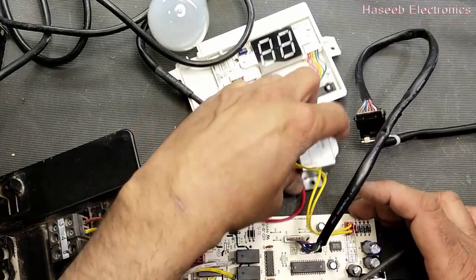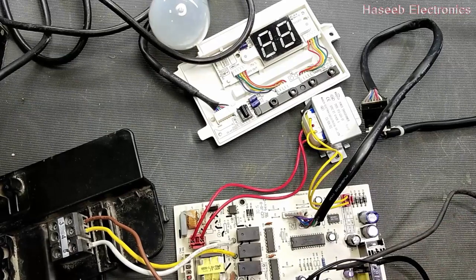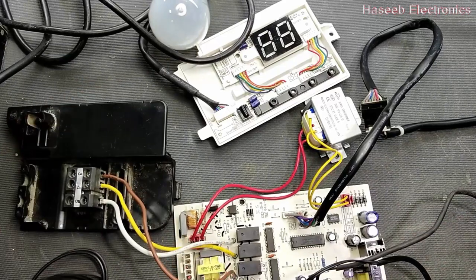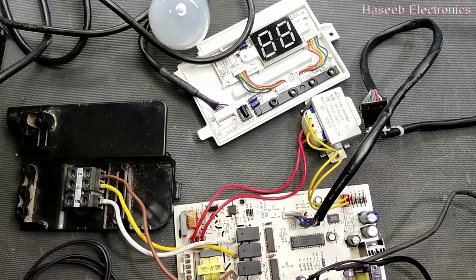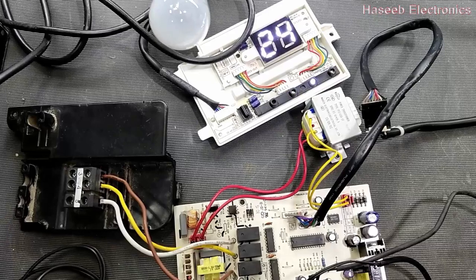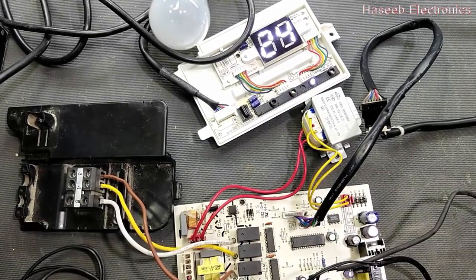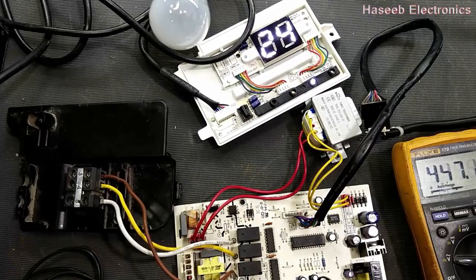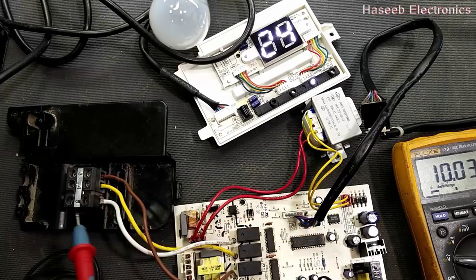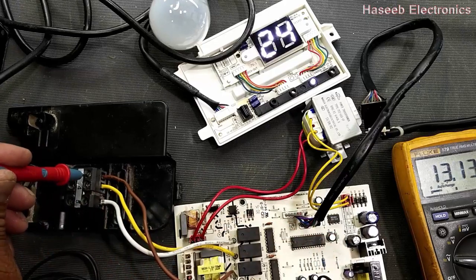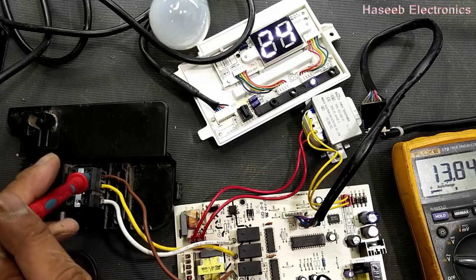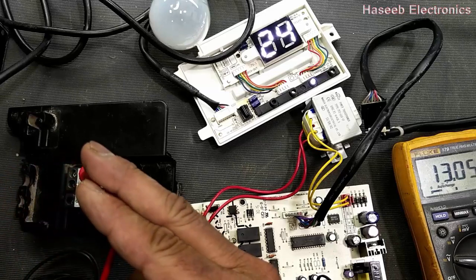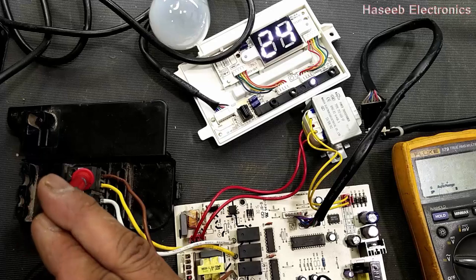Now I will share the most common failures of this board. First I have to turn it on. Now it is powered on. Set the multimeter to AC voltage. Put one lead at this common pin and connect the second lead at the brown lead. That is for the compressor.